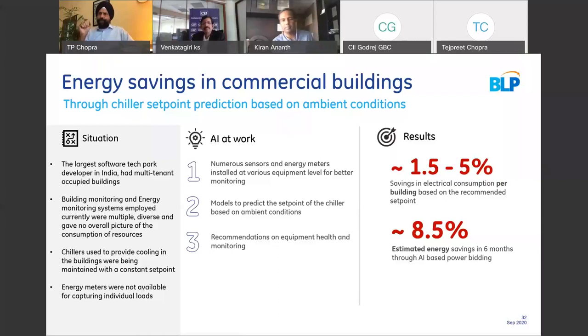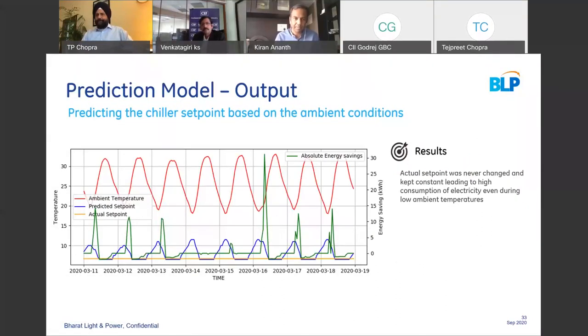As a result, just by changing the set points based on these algorithms over a short period, we achieved—depending on seasonal impact—between 1.5% to 5%, and actually saved over 8% of energy costs in just 6 months. This is just a quick example of some of the output.